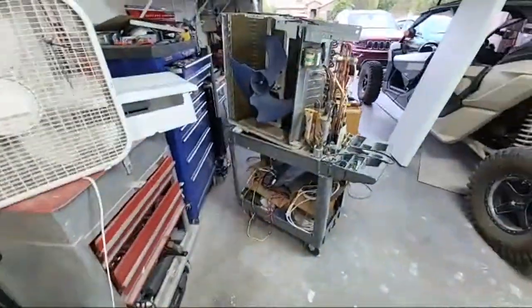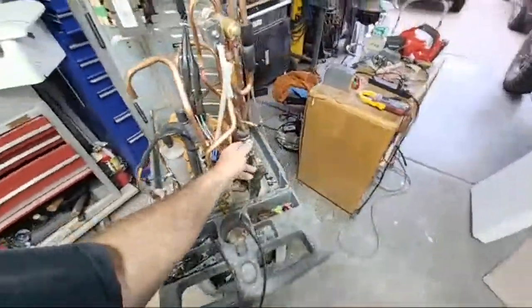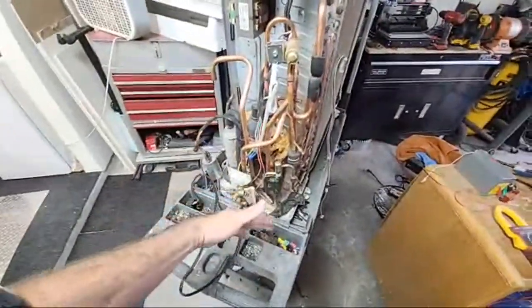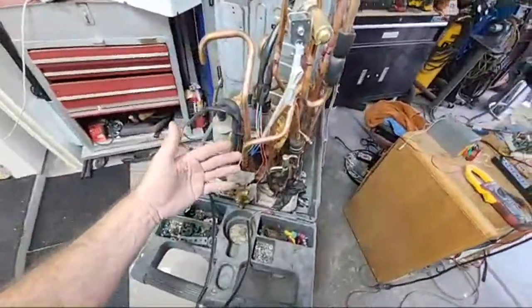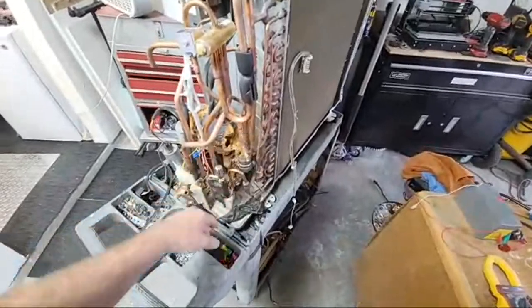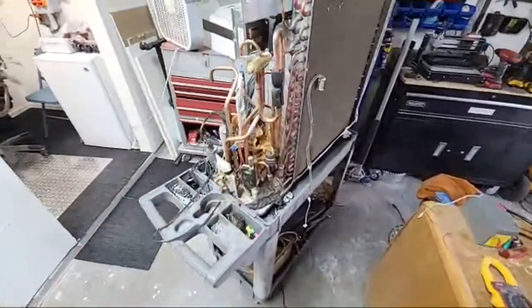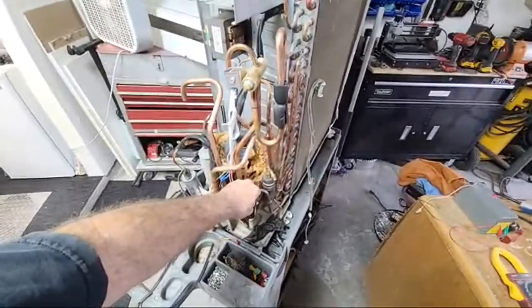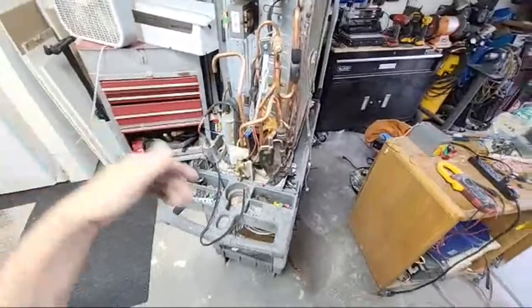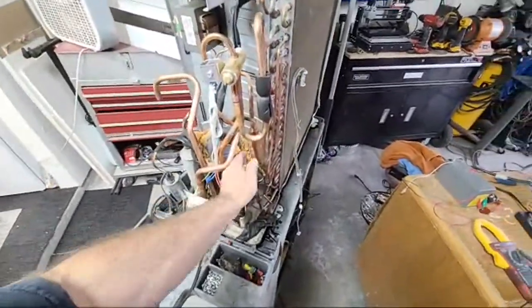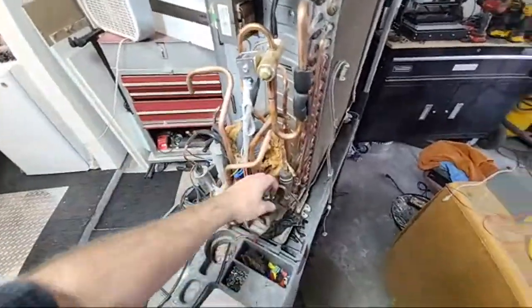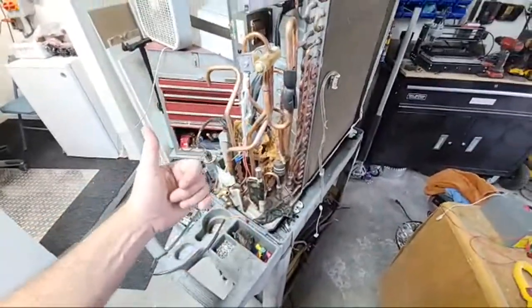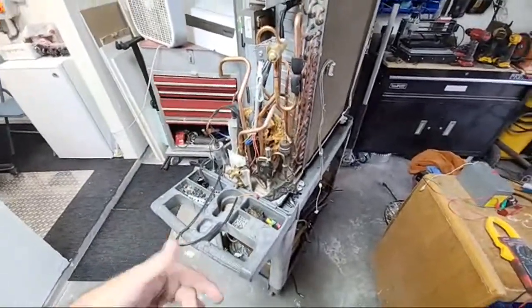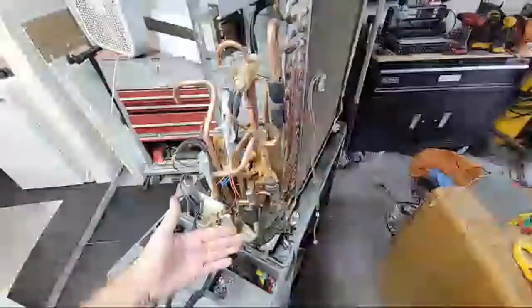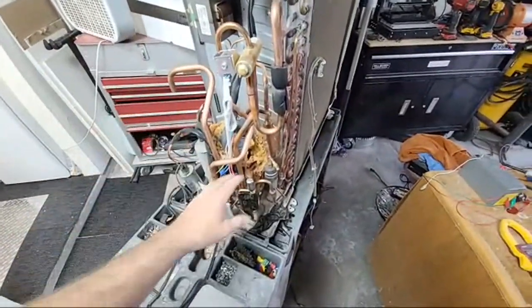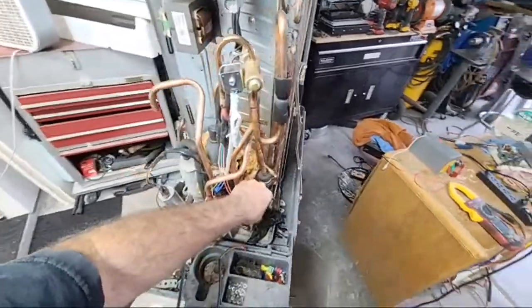Like I think I was explaining before, probably in the video clips I didn't use, basically what you do is you go to a starting point, and then you start looking for correction. You wait a few minutes, and you're like, this is the coil temperature and this is my suction temperature, that's superheat. So you start modulating to get the right superheat, and right when the unit stops, you write that position into memory, and then you wind down the expansion valve and close it. Then on the next call for cooling, or for heating the hot water, the expansion valve is going to open right where it left off. It's going to be close enough that it works pretty well, but the superheat's going to be off, and then it's going to start modulating. After a couple of minutes it'll start adjusting, so you wait a minute or two, and then make an adjustment every 30 seconds or something.